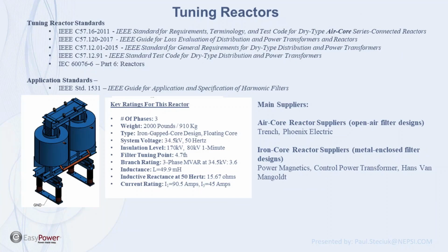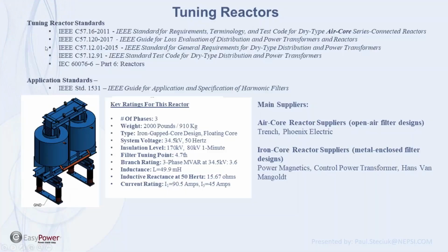For tuning reactors, and I show here an iron core reactor here. For tuning reactors, there are some standards. There are no direct standards that dictate the tuning reactors. My recommendation is to always go to a reputable tuning reactor supplier. In the United States, I only know of 3. In Europe, I know of 1. So there's not a significant number of those.